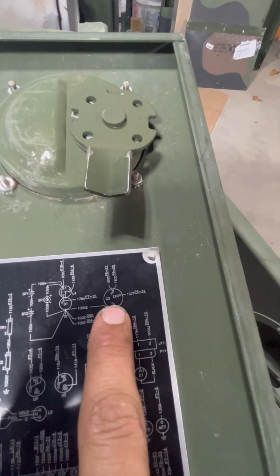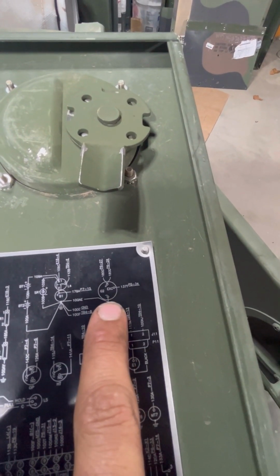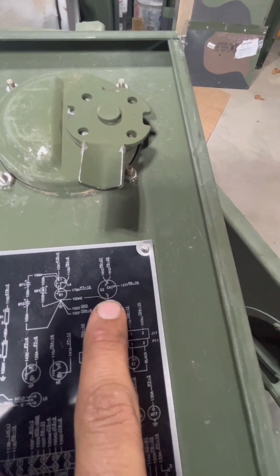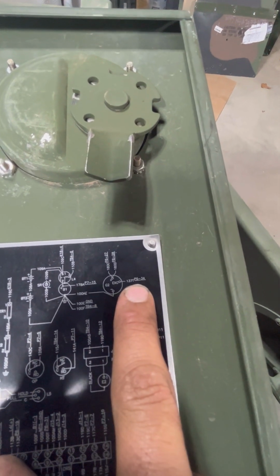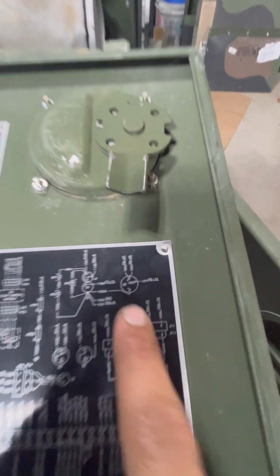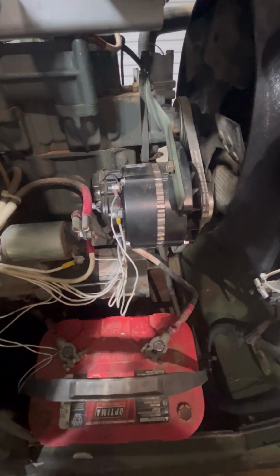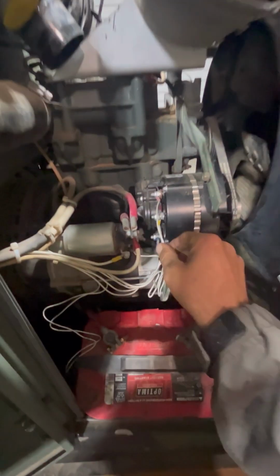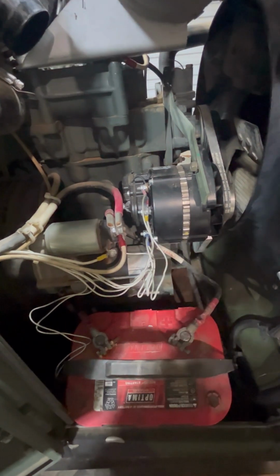And I went to the generator, the 24 volt generator on the side. And as you can see, 137T is supposed to be wired into the exciter. But back here, I don't know if you can see that, it's wired into the AC tap, not the exciter. I also double checked that with an MEP-802 that I have sitting outside. So I'm gonna swap this wire and see if that fixes our issue.